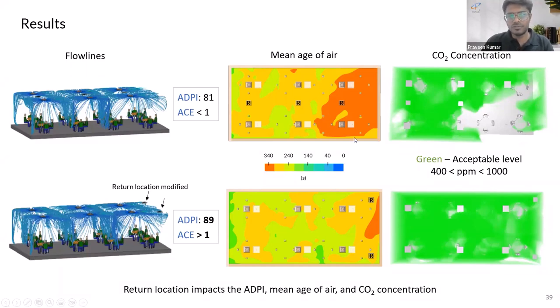So what we did was move the return locations, and we saw a lot of improvement, a reduction in mean age of air, and the CO2 concentration went to the acceptable level throughout the occupied space. This was wonderful, and it got reflected in the air change effectiveness as well, moving above one. So the return location does have an impact on ADPI, mean age of air, and CO2 concentration.